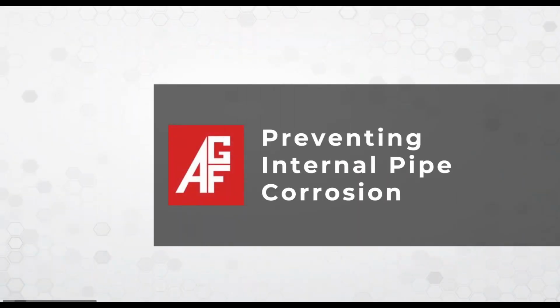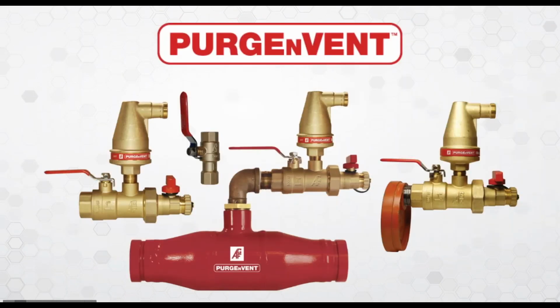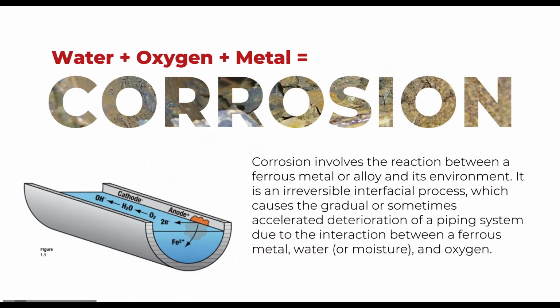Now I'm going to jump into corrosion, which is really one of the single biggest expenses on both wet and dry systems. If we focus first on corrosion on wet systems, I don't think I need to go into too much of the science side of corrosion, but certainly if anyone has ever left their bicycle outside, they understand that if you put water and air or oxygen and steel together, you're going to get rust. You're going to get this oxygen-based corrosion.